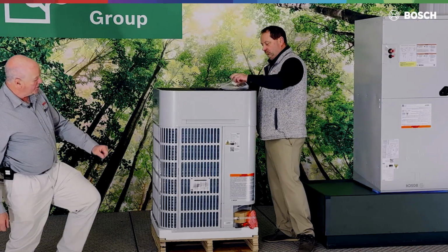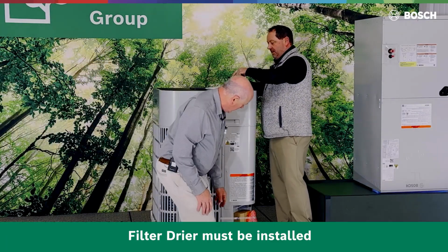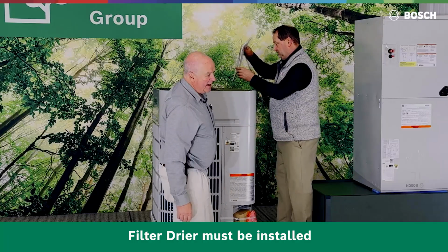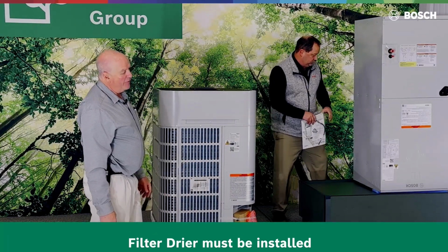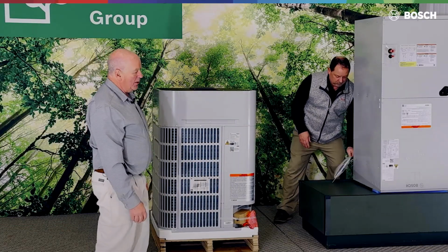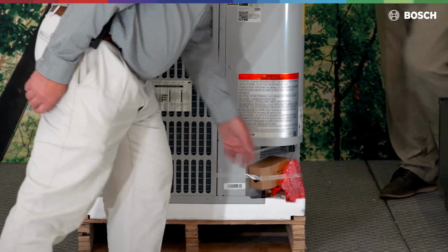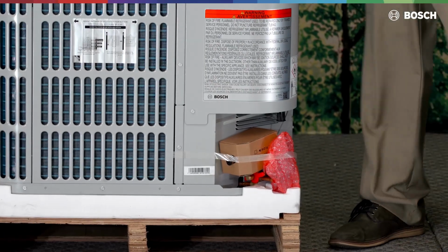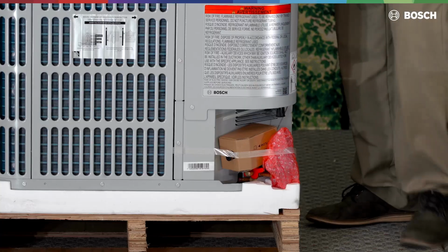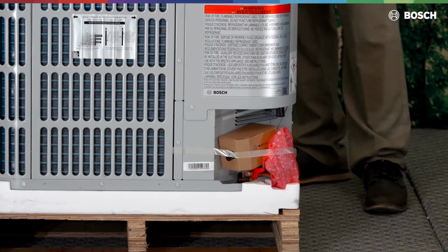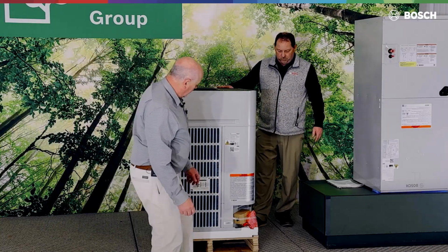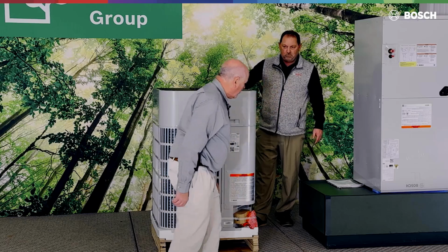So we got some things down here tucked away underneath. This is one, it's the filter dryer. It needs to be installed. It is a bi-flow filter dryer that must be installed. That is a steel canister. If you braze that canister in and you burn the paint off the end bell, it will leak after periods of time. I'd prefer to have that filter dryer installed indoors, out of the weather.